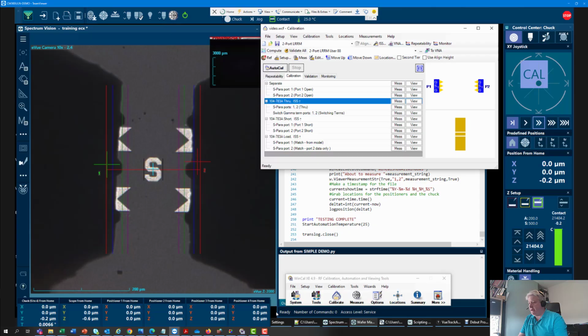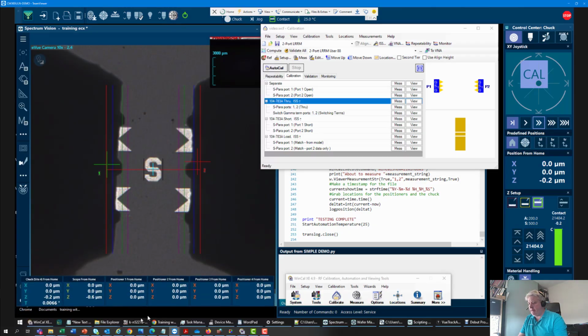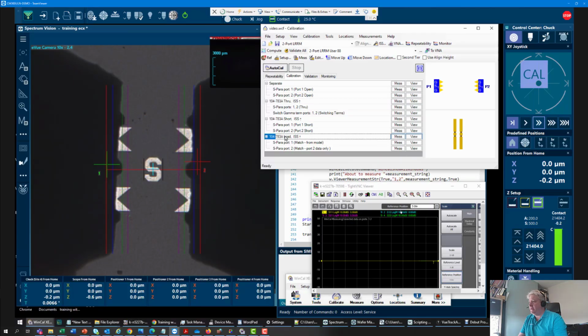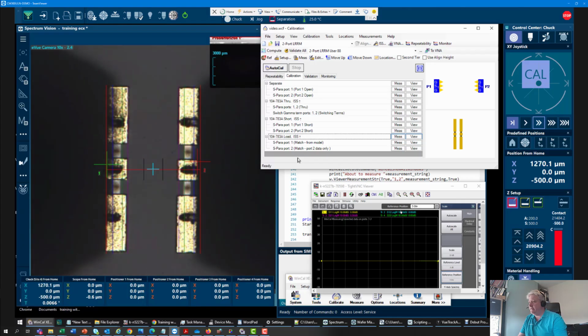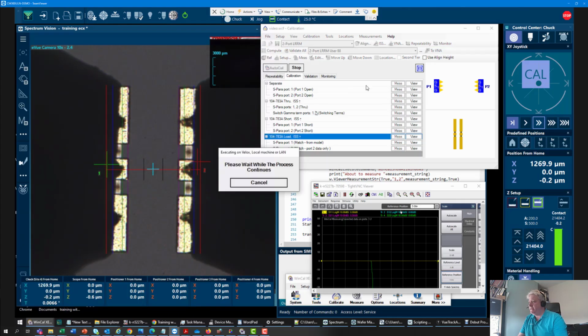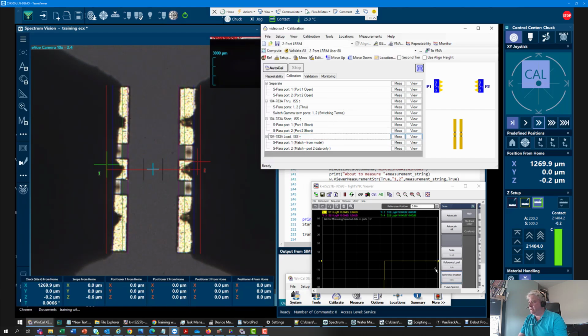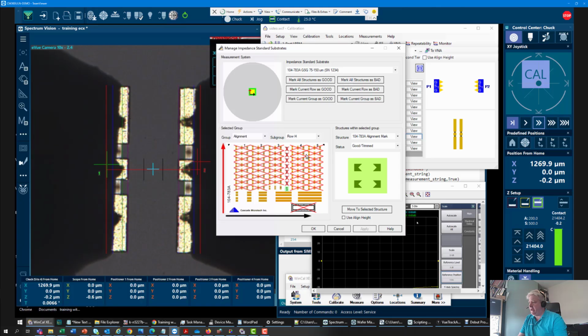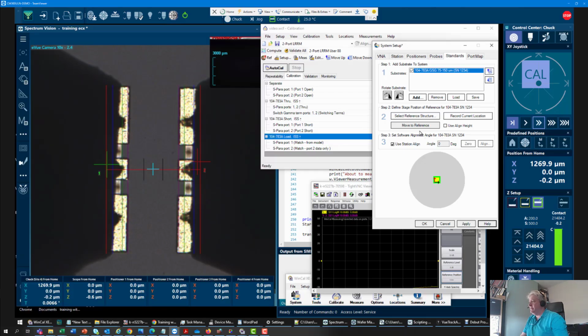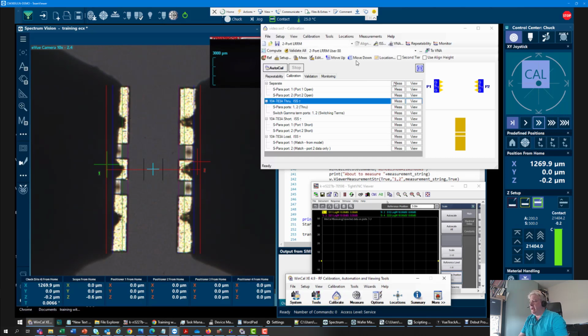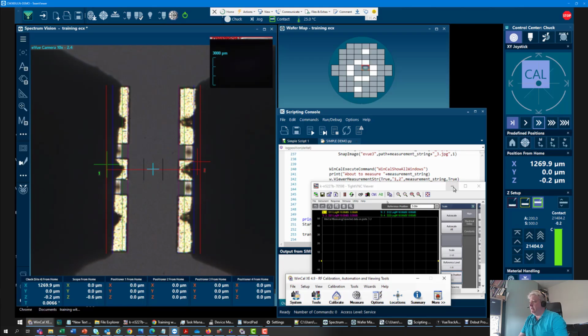I have access in here to see what my VNA is up to, so you can see my VNA. And one check you can do is just maybe move to, just check everything all works for the load. Now I've used this location a fair bit, so you can see it's calibrated, so it should just fall off like a cliff. I've used this location quite a fair bit, so I'm going to just change it. You'll notice that I deliberately have locations set to be bad because I don't want them used. It's going to use the topmost, leftmost. I'm going to force it to use this one, and you should be checking against your map to make sure these are trimmed locations, or you could measure them using a B1500 or similar parametric instrument. Okay, so I'm going to use that site for my calibration when I run autonomous, so that all looks fine.